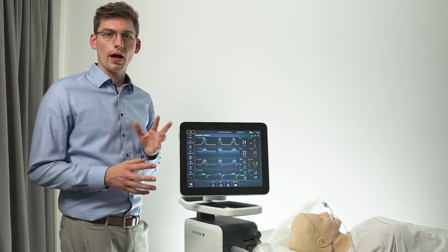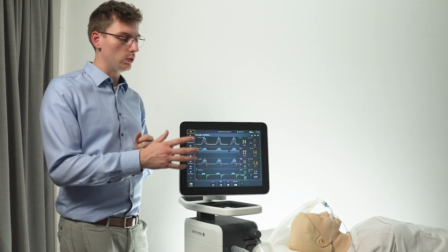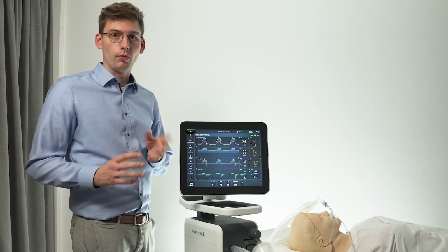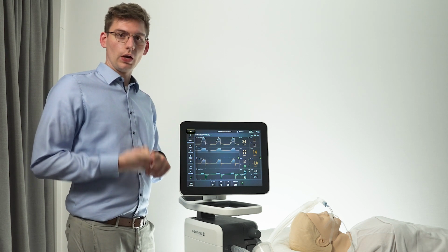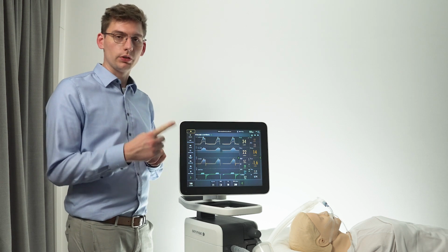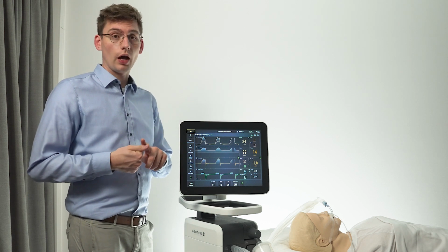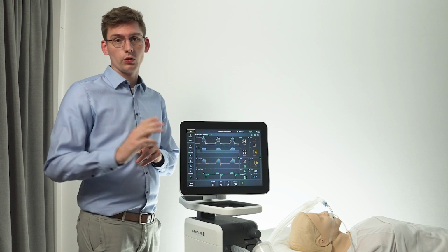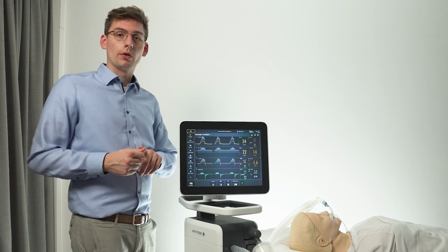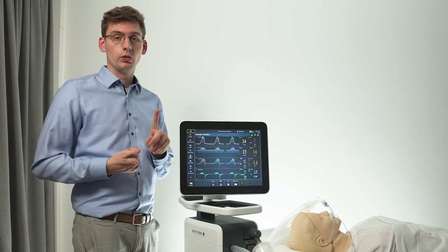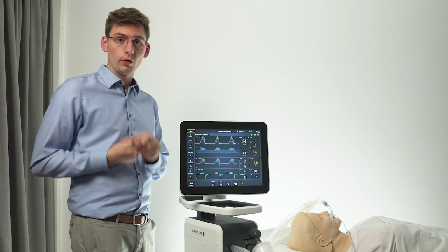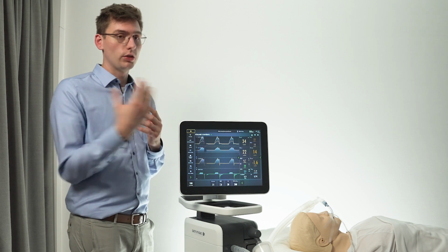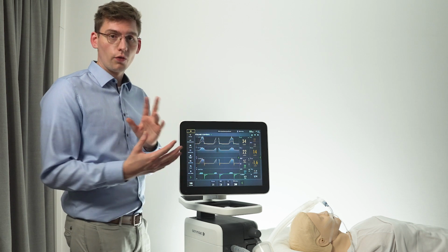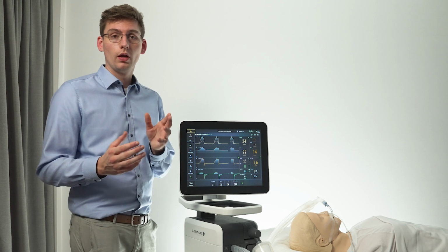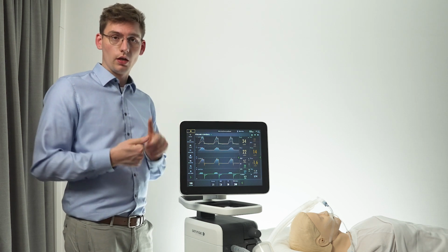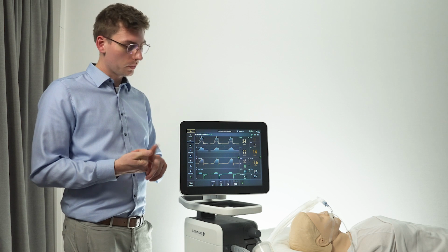What I'll discuss right now is how to manage the esophageal balloon over time in your clinical patient. The first very important thing to know is that you have to confirm the positioning of the balloon every time you want to do new measurements. So if I were to leave the patient and come back 2 hours later to do new measurements, I would do these steps that I've shown you before to confirm adequate positioning and filling again, to make sure that the data that I'm getting from the ventilator is reliable and can be used to make clinical decisions. So that's a first important step to know.